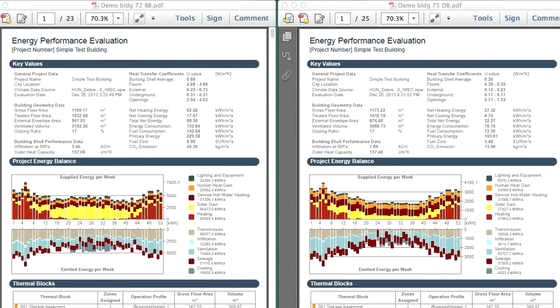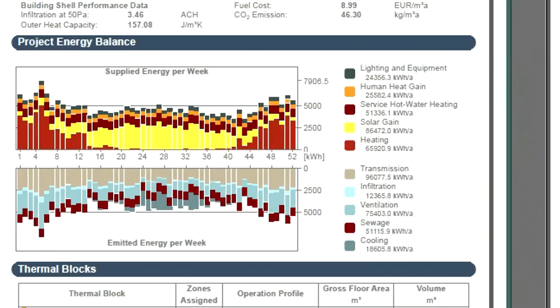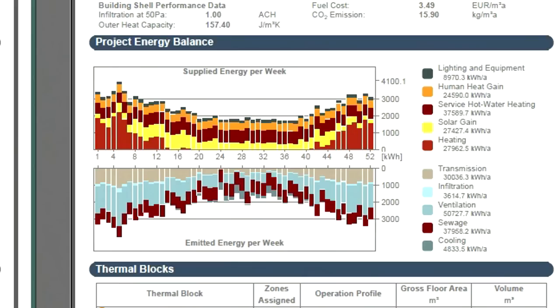Both primary energy consumption and fuel costs are reduced by half compared to the baseline project. As a result of the low energy building solutions — for example better thermal insulation and air tightness — the project energy balance displays a massive reduction in energy flows. The maximum supply energy per week in the baseline project was over 7,900 kWh, while in the improved project it is less than 4,100 kWh. The benefits of smaller building systems, heat recovery and on-site electricity production show in the reduced carbon footprint.